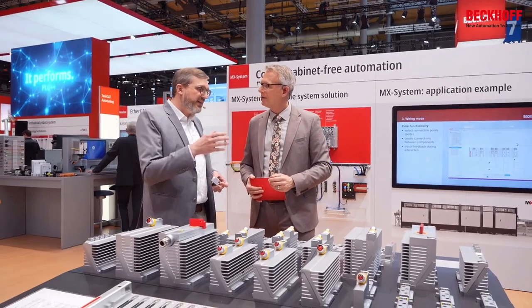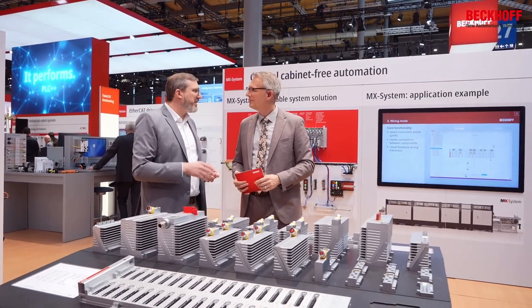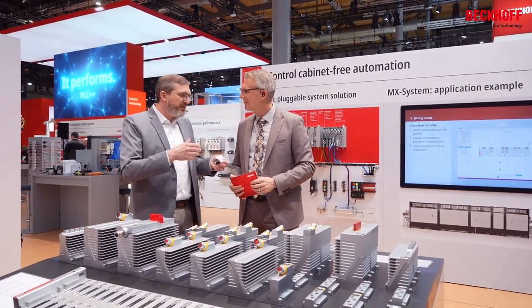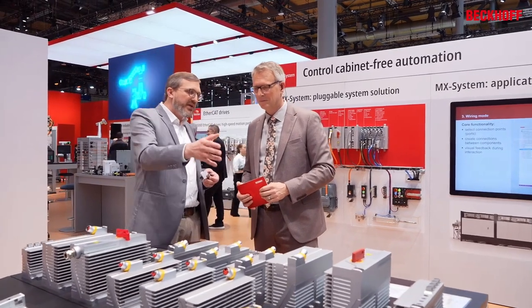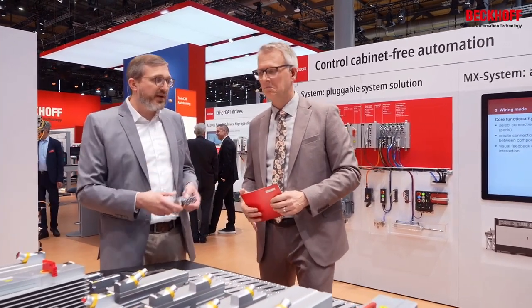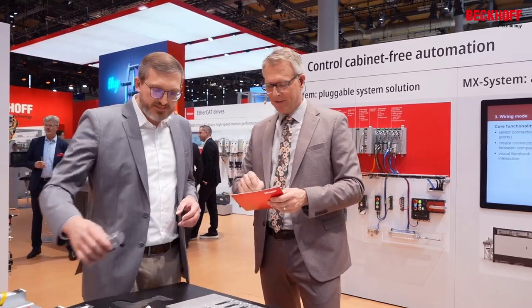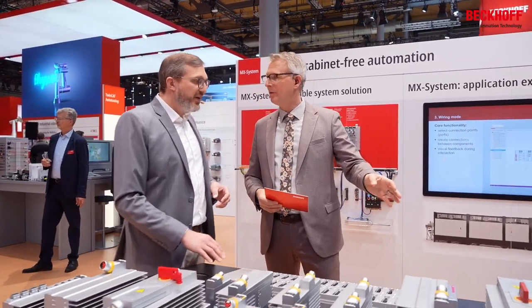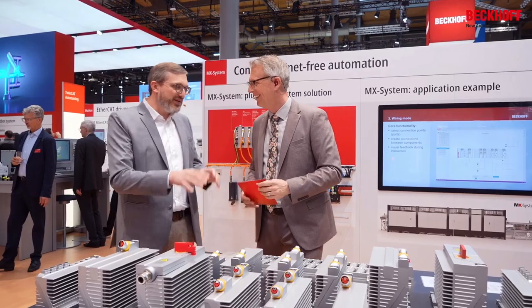So the designer can calculate the power consumption or the current consumption from each and every power supply. Let's say you have a lot of drives in there, and you would exceed the maximum power the power supply can deliver, and then the designer would give you a warning: that might be a bit too much here, you're using 150%. And then you can rework stuff, maybe put another power supply in, and work with the feedback. So I don't need my notepad and say 5 amps, 10 amps plus 5 amps, like 20, and the power supply only at 15. This is done. This is all done in the designer, yes.